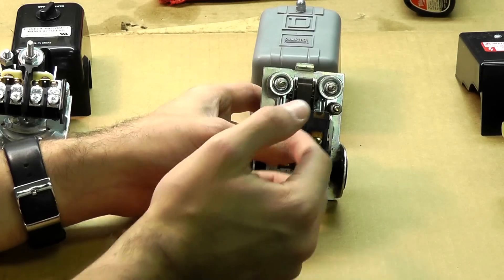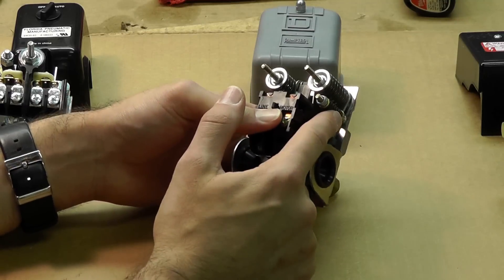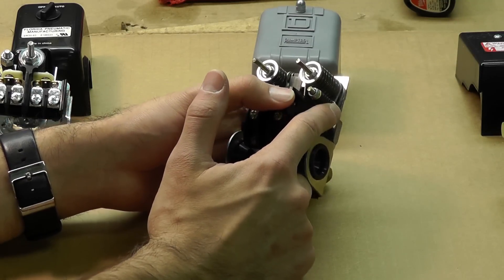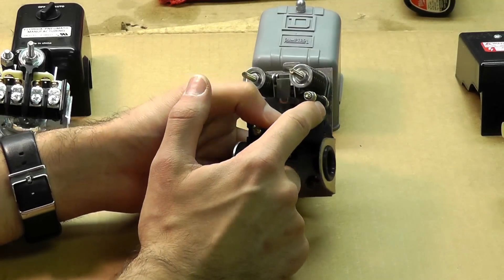Now this is the differential, which is the difference between the high-end pressure and the cut-in pressure. So if you do adjust this clockwise, it will turn and increase the high-end cutoff pressure. So it cuts off at 125.